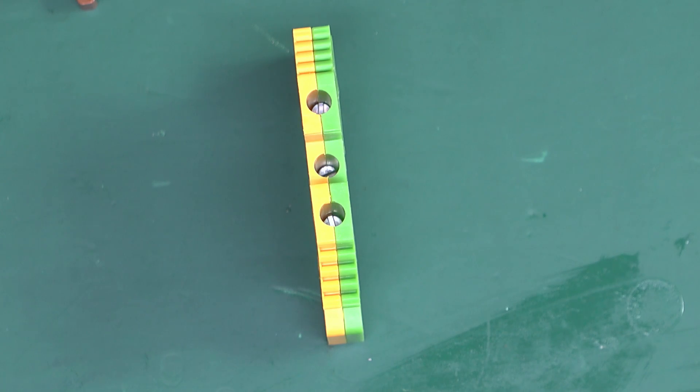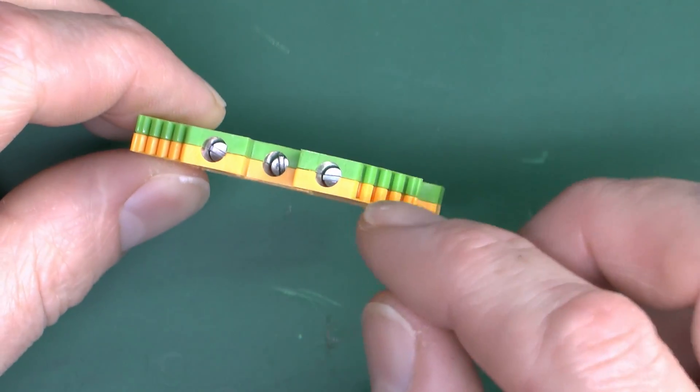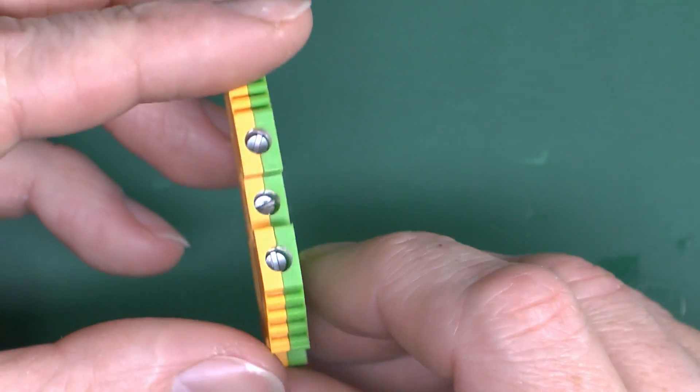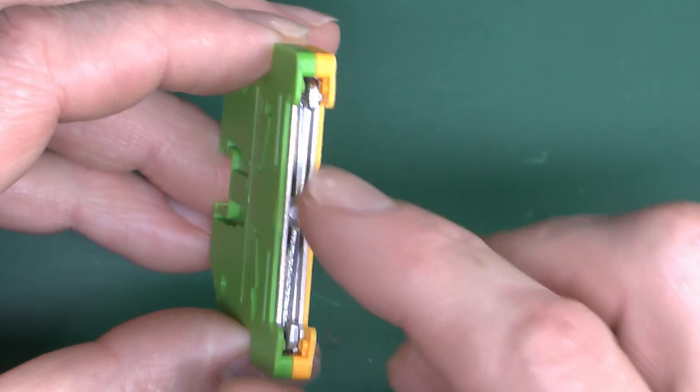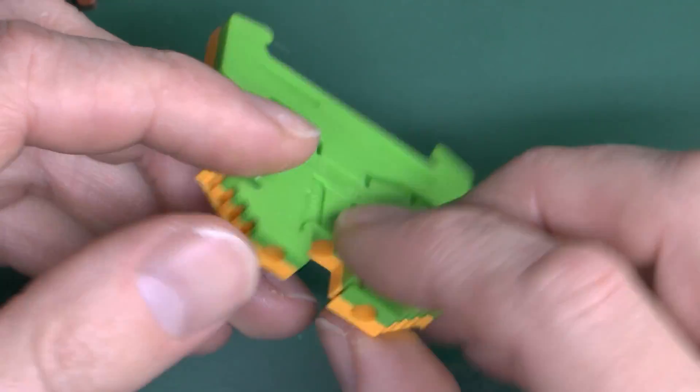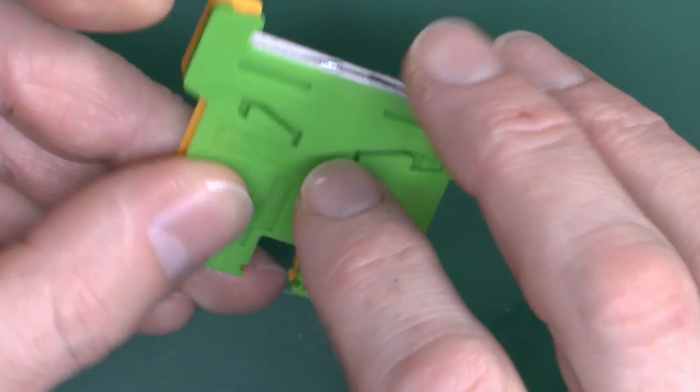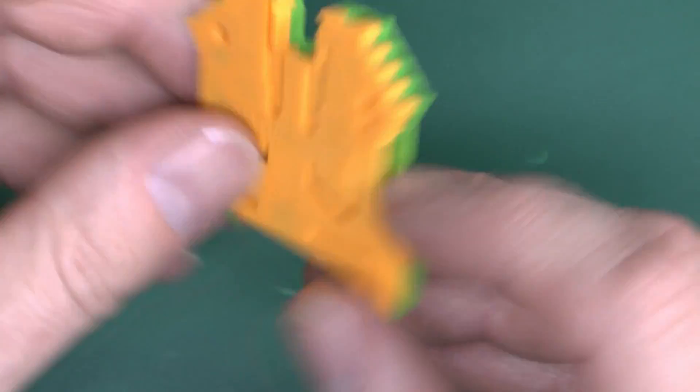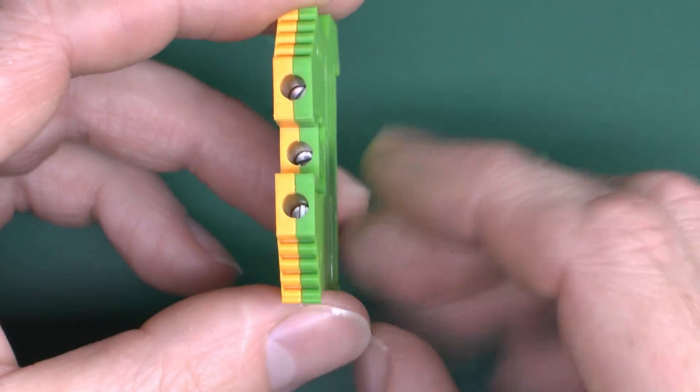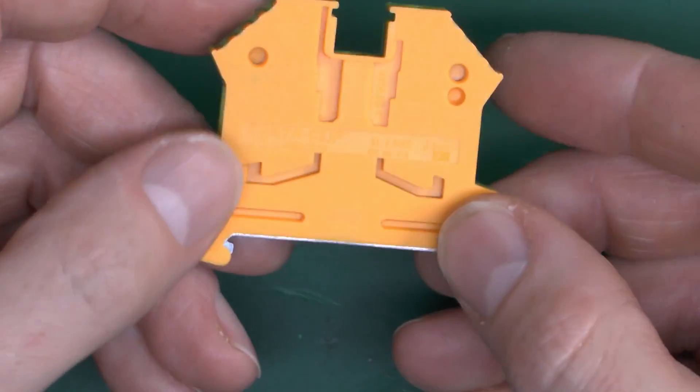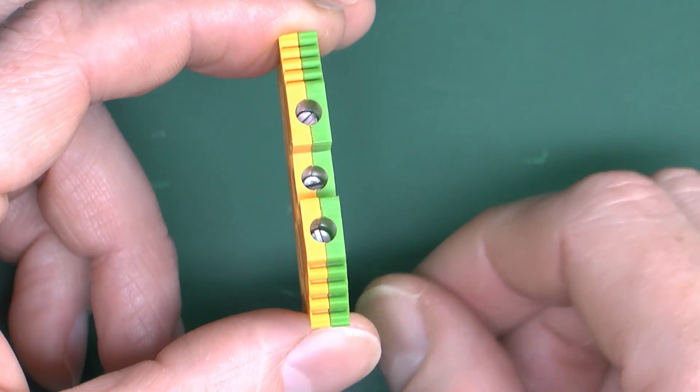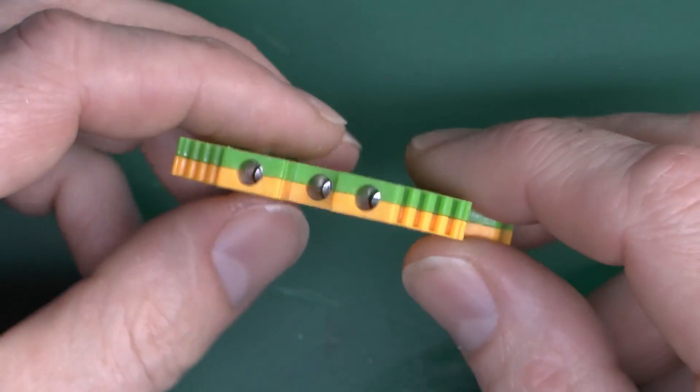Now the other colors are all exactly the same, other than the color. Apart from the earth ones here, which as you can see are green and yellow, sort of half and half, these are actually fully enclosed on both sides. And an important difference here is that the bottom has a metal contact here. So when you attach it to the rail, these pieces here will actually clip onto the rail. There's a screw in the middle on this one, which is tightened up, and that actually grips onto the rail very securely. So with the earth ones, you've got the same wire in each side, which are joined together. But additionally, those two are actually joined to this strip here. So then they're actually attached to the metal rail as well. And of course if that's in a metal cabinet, that also means that the metal cabinet is also connected to the earth as well.